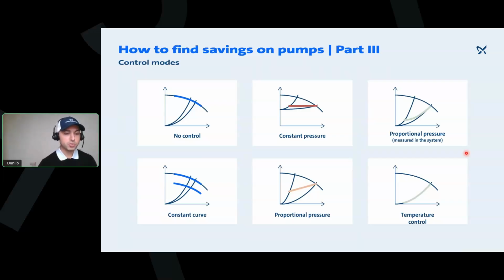What you want to do is track efficiency points, right? And run that pump based on efficiency. That's how you want to optimize your pump sequencing, right? And all of that is about what is better. In that case, are we running on a constant curve? Are we running on constant pressure, right? Newer systems allow you to keep the pressure and vary just the flow. Now that could also, depending on your system, as your pump flow goes down and you keep that pressure, the efficiency goes down as well, right? So these curves are always about looking at efficiency. You have to maximize the highest efficiency for your application.